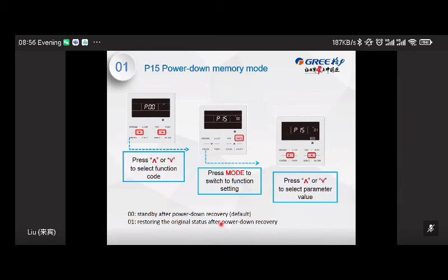Next one, P15, power down memory mode. This is for the memory function. The default setting is standby after power down recovery. Yeah. So when the power is lost and power recovers, the units will be standby. That's the default setting. However, you can change the memory function to restore the original status after power down. Okay, if you set this one, the previous status, for example, is cooling, and then when power recovers, the units will start the cooling automatically. It will remember the previous running mode and restore the previous status. Okay.